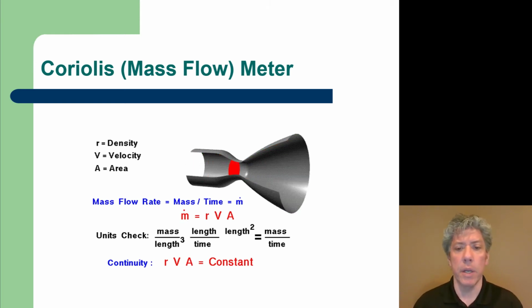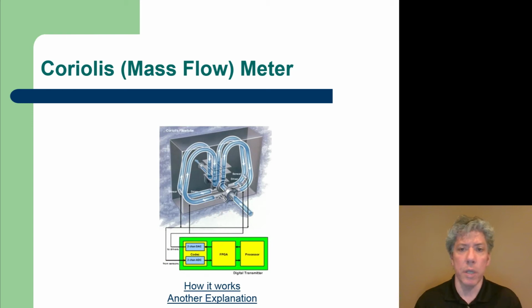And of course, we're using a continuity equation here to calculate the mass flow rate, but we're really not measuring the mass flow rate directly. There are meters, or sensing devices, for measuring mass flow rate directly, and at least this type, the Coriolis type, works on the principle of inertia. So as a stream is flowing, it has mass and therefore has inertia and doesn't want to change its direction. And so the pipes that you see here, these bent tubes, are oscillated on purpose back and forth. The fluid resists that oscillation and causes oscillation in other areas of the pipe. When you measure that resultant oscillation and look at the phase difference between the exciter and the responder, you can actually calibrate and figure out the mass flow rate.